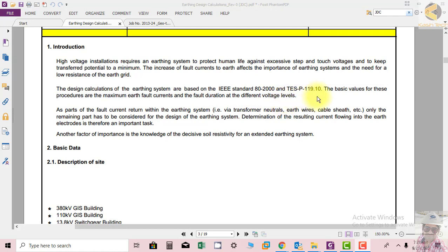If you have a substation with three different voltage levels, 380 or 110 or 11.5 kV, whatever, each voltage level normally has a different fault level and duration. In most of our cases, the short circuit level could be like 60 kiloampere for 3 seconds. Substation protection should be able to isolate the fault within this time.